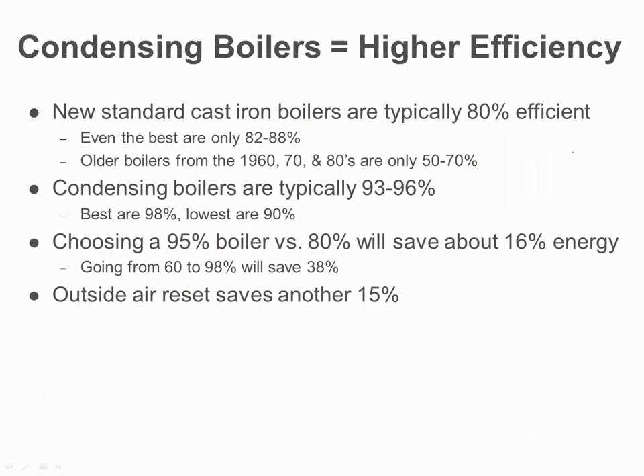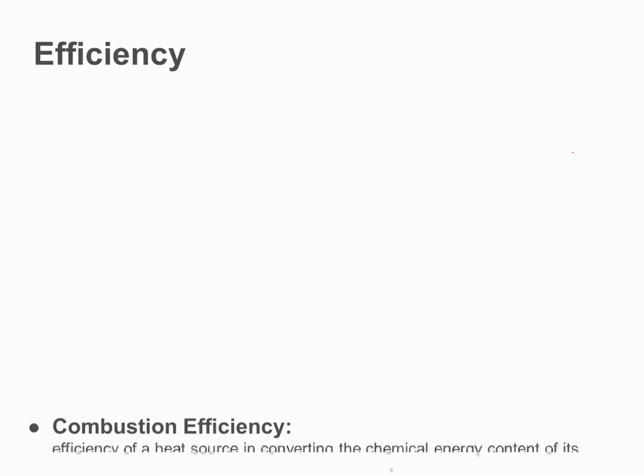Additionally, if you add outside air reset to a boiler system, you could save another 10 to 15% energy. We'll talk about that in a minute here as well. There are 3 different terms of efficiency that we use in the hydronics world for boilers. There's combustion efficiency. So this is if I take my gauges and I measure the air temperatures coming through the exhaust pipe, I can calculate the efficiency of the boiler, right? So this is basically, I measure how much is going up the stack. I assume everything else is going into the building, right?